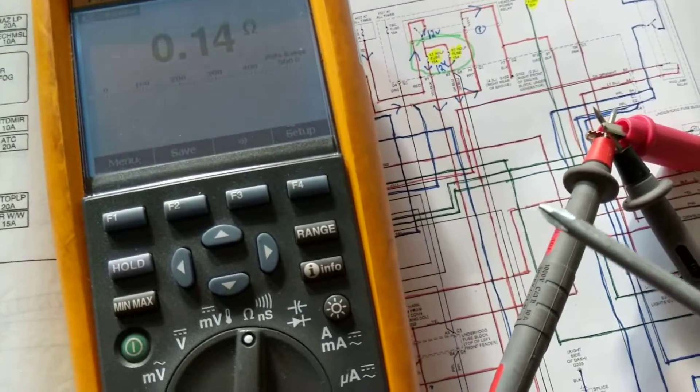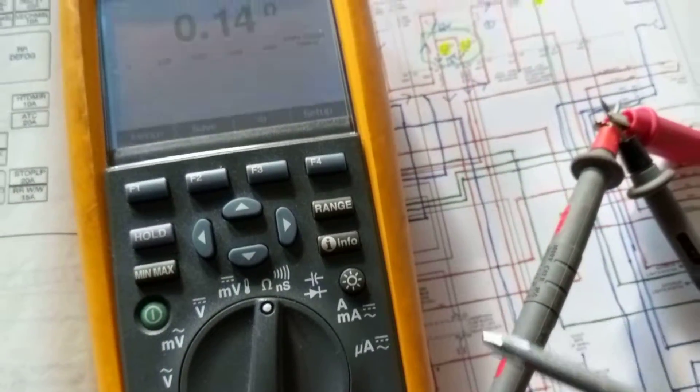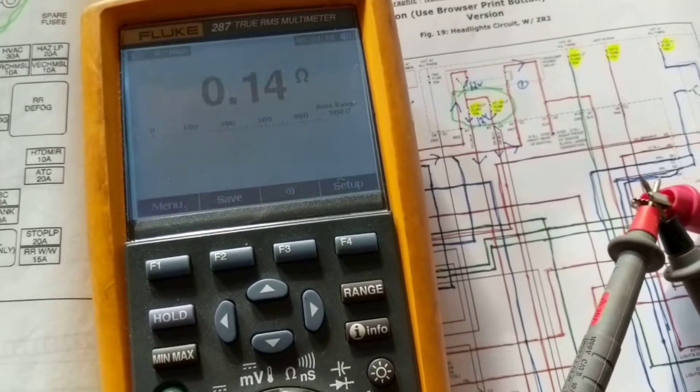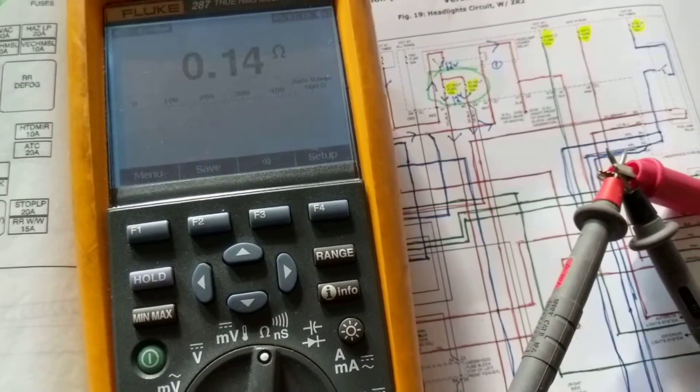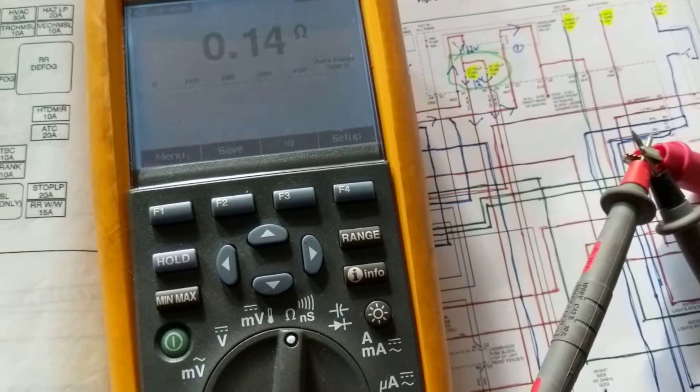First thing is you want to make sure that the leads are good. I shorted them together on the ohms scale, and as you see 0.14 ohms. That's very good. Now if it measures one ohm, that's not good.